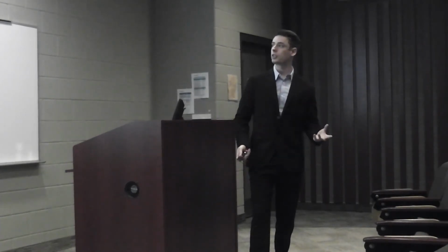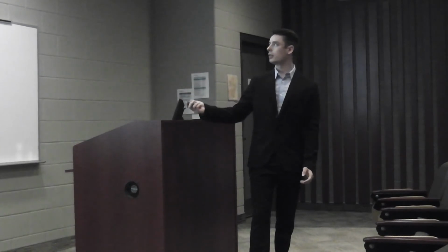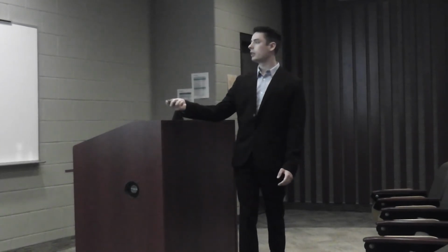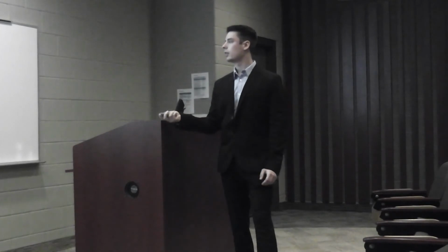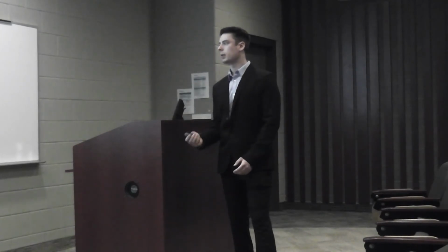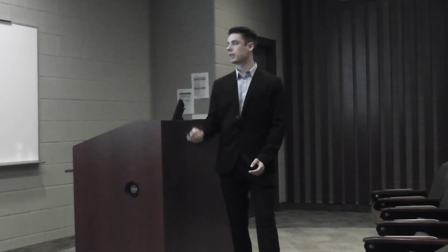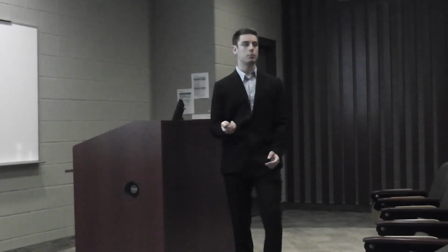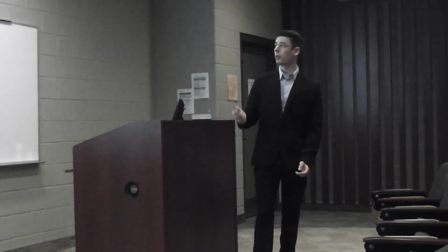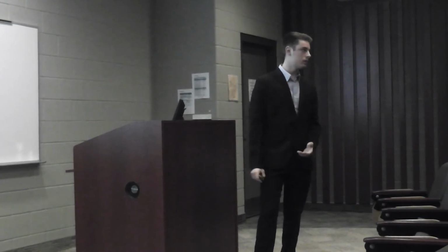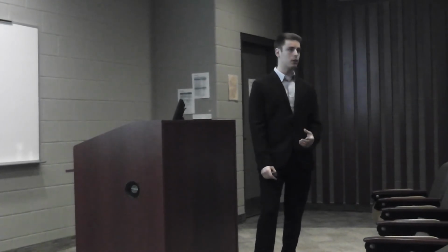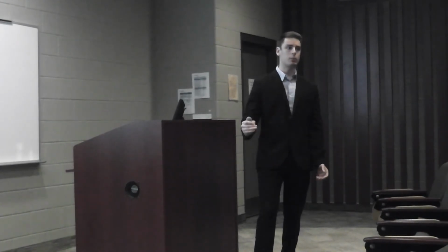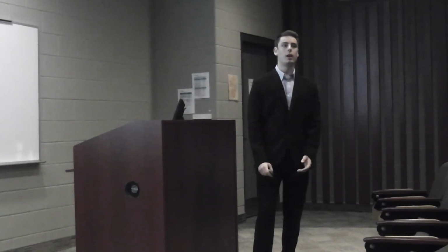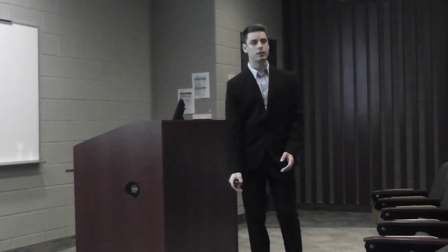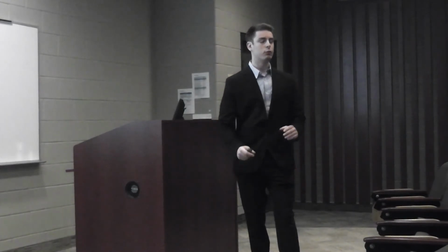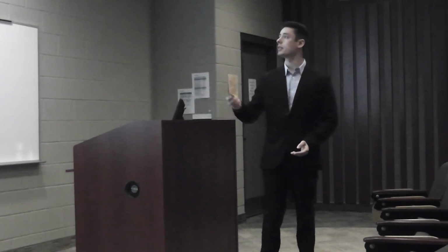So it's just conduction. There are our values, the heat transfer formula that I used, and I came up with 466 BTUs an hour that you're losing. So over 16 hours, that's 7,460 BTUs. So yes, it is possible, since 7,000 is obviously not the same as 18,000. You still have stored energy to not go below that temperature. So it's possible, but we'll see it's not feasible, because it's such a small application that you're really not paying much for electricity anyway.